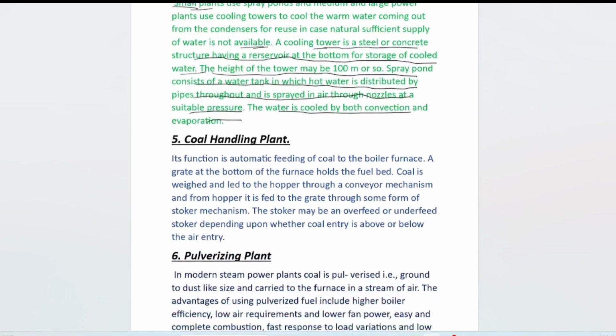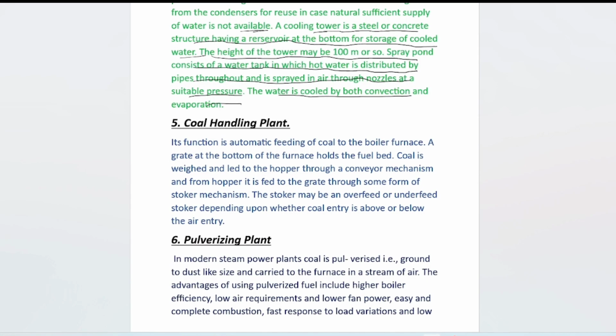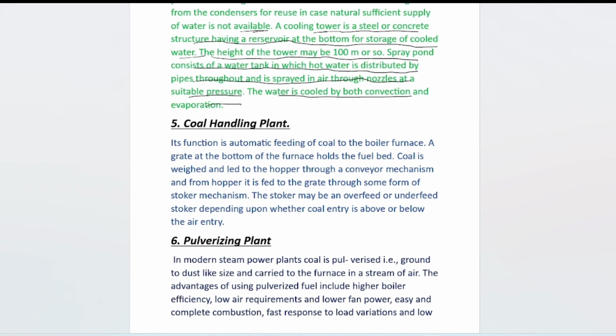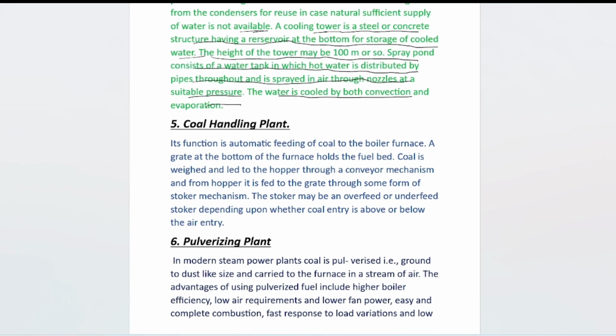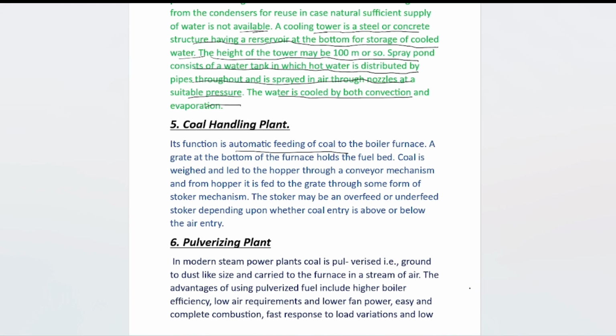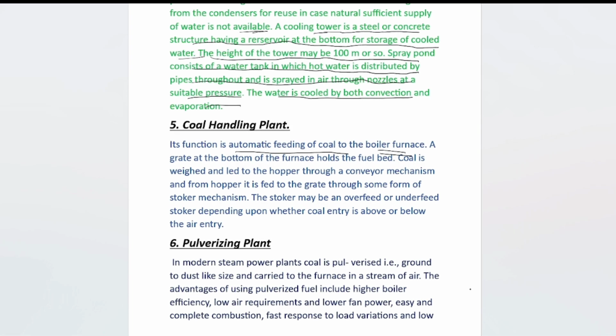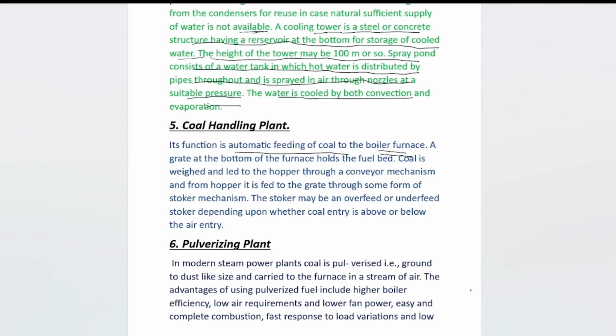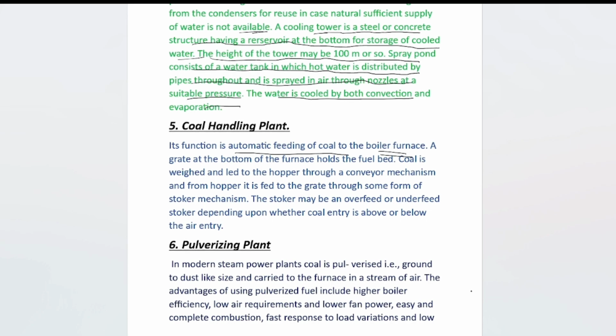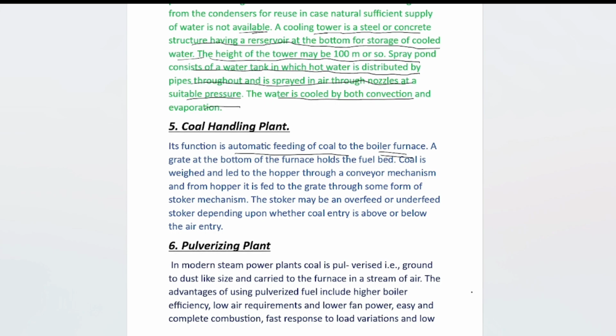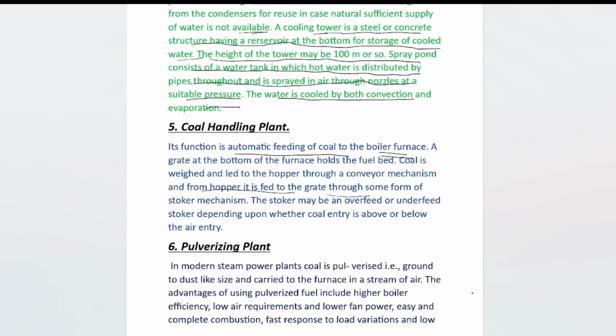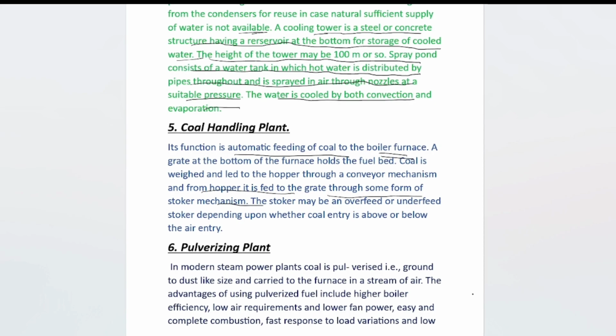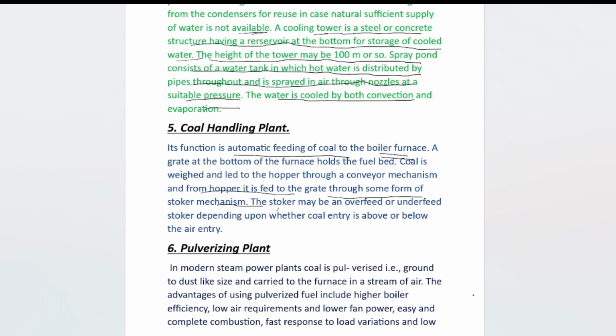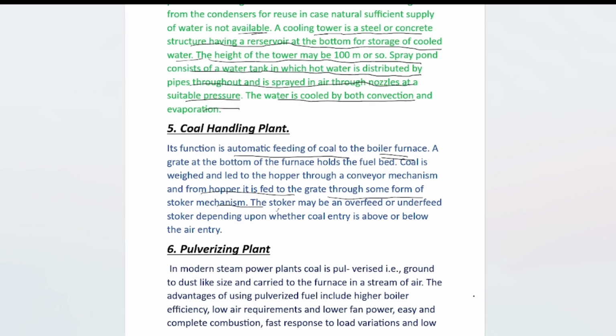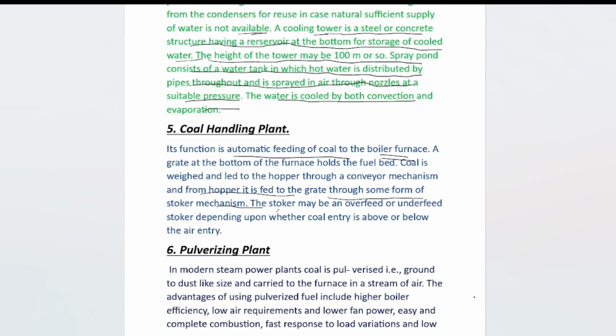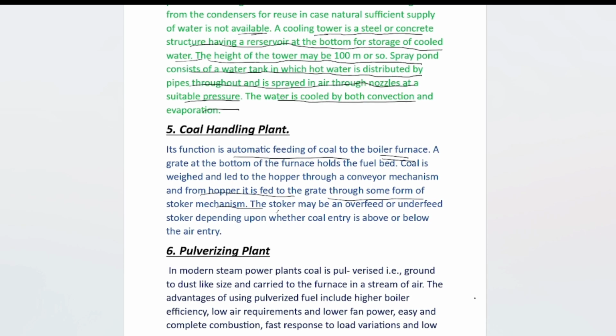Fifth point is the coal handling plant. In modern days, its function is automatic feeding of coal to the boiler furnace. A grate at the bottom of the furnace holds the fuel bed. Coal is weighed and led to the hopper through a conveyor mechanism, and from the hopper it is fed to the grate through a stoker mechanism. The stoker may be a side-feed, overfeed or underfeed stoker, depending upon whether the coal entry is above or below the air entry.